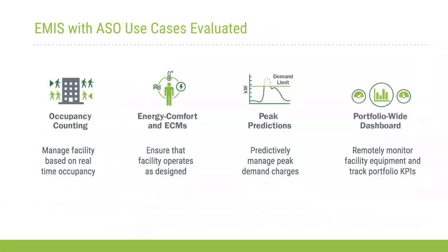There are 4 capabilities that we evaluated. Occupancy counting technology is the primary capability that informs and enables the EMIS with ASO. The occupancy data is used along with thermal modeling, weather data, and machine learning algorithms to implement the energy conservation measures, or ECMs. This includes things like optimizing air handling unit fan startup scheduling based on when people are arriving and the optimum time, and then ramping air handling unit fans at lunchtime and at the end of the workday, reflecting the change in occupancy pattern during the day.